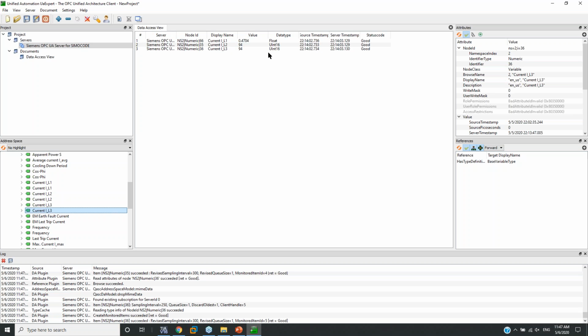Start my SIMOCODE, and now it's running at 93, 94% of full load amps. Turn the current down on my demo, and now we're down to 60% or 0.29 amps. All this data, you can come in here and monitor the items, and you can also set the scan rate of how much you want to save in your historian. It's that quick and that easy.